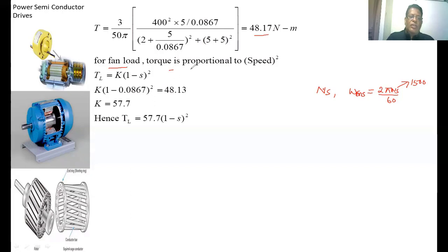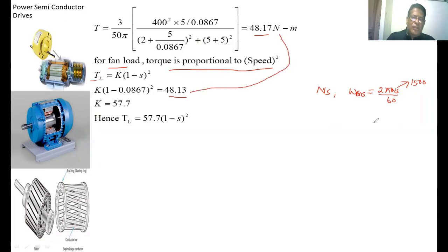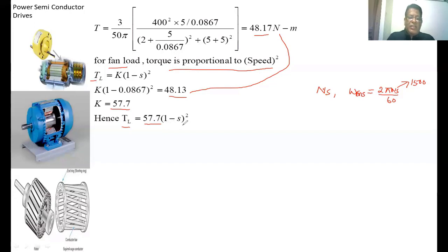For a fan load, the torque is directly proportional to the square of the speed: TL = K × (1 - S)². We now find the load constant K. Substituting the rated slip of 0.0867 and the rated developed torque of 48.17 Nm, we get K = 57.7. So the load torque expression is TL = 57.7 × (1 - S)² for any value of slip S.